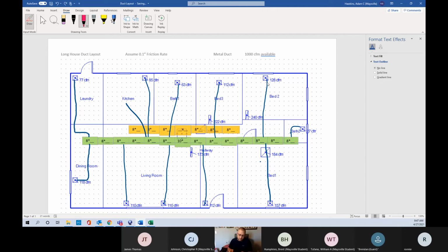Now back to your 0.1. So go to 0.1 and move 126 CFM. About 6.5 in the round up. Yeah, and I'll go ahead and tell you, most people are going to put a 6-inch in there, just because it's what we do. So you go to every bedroom, you give every bedroom a 6-inch, and I'm guilty of it too. Every bedroom gets a 6-inch, unless it's a big bedroom and it gets an 8.